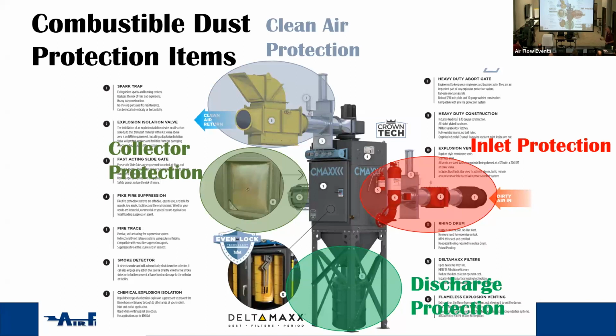And then on your return side, you need a clean air protection. So if you're gonna return it to the space, you need an abort gate. Abort gate is not an explosion protection device. An abort gate is the fire protection, fire prevention, smoke prevention device that's on there. So all the abort gate does, and the only reason it's not an explosion protection device, it does not operate fast enough to stop that propagated flame ball from going back into the building. So on the clean air side, this is the fire suppression, fire prevention device that just aborts the smoke if a fire occurs in your collector. The explosion protection part of it is your inline deflagration arrestor.